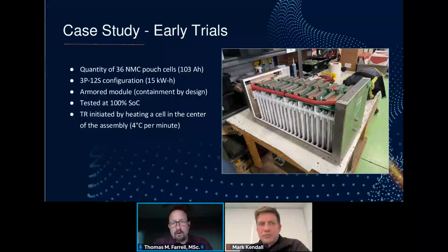And as I said before, thermal runaway was initiated by heating the cells internally at a low rate, right around 4 degrees Celsius per minute. And 9540A gives you a range of 4 to 7. We find the slower you go, usually the more energetic things are when they fail, because it gives more time for heat to disperse into the rest of the pack and put everything on a little bit more of a hair trigger.